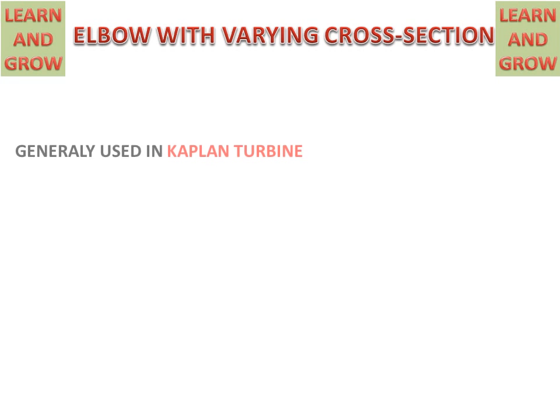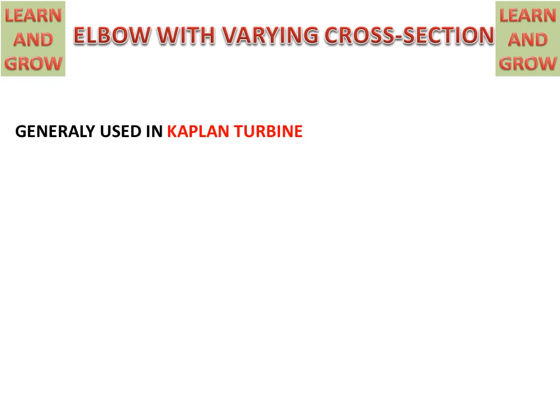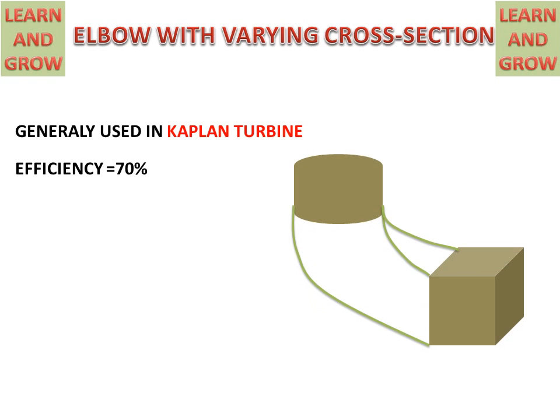Elbow with varying cross section area. This is generally used in Kaplan turbines and its efficiency is 70%. The upper part has a circular cross section and the lower part has a rectangular cross section. Water will enter from the circular cross section and exit from the rectangular cross section.